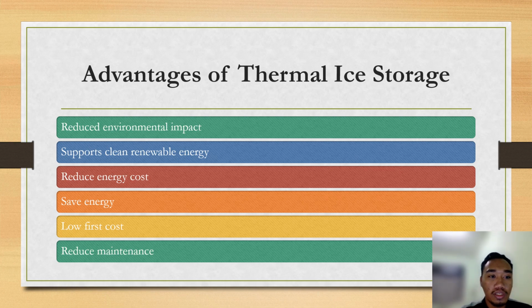And the last one is reduced maintenance. By using smaller capacity equipment, it reduces the need for maintenance. The thermal ice storage itself does not include too many moving parts, therefore does not require additional maintenance.